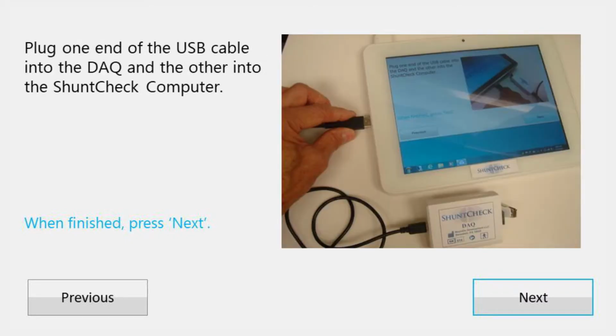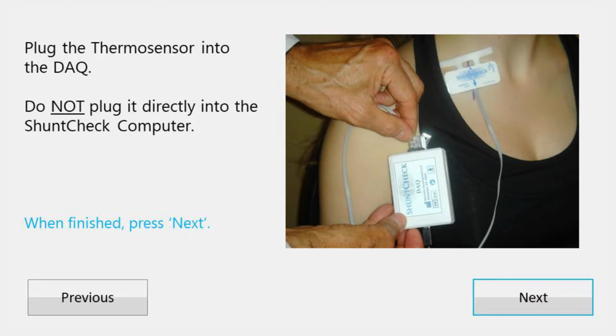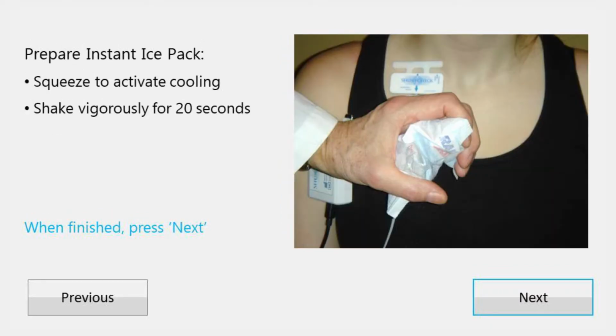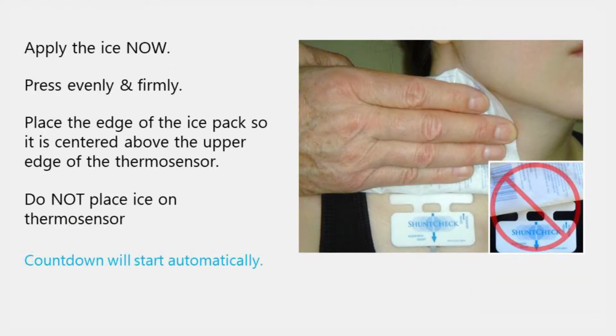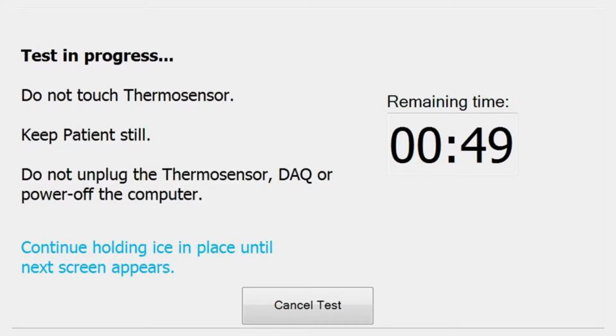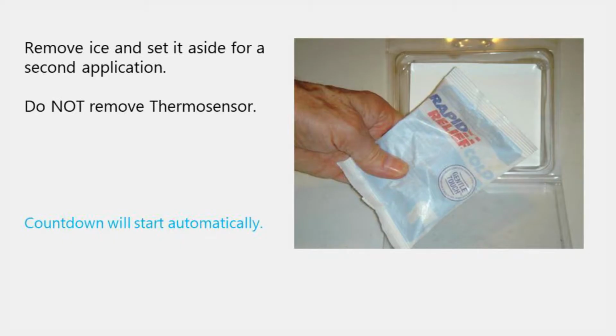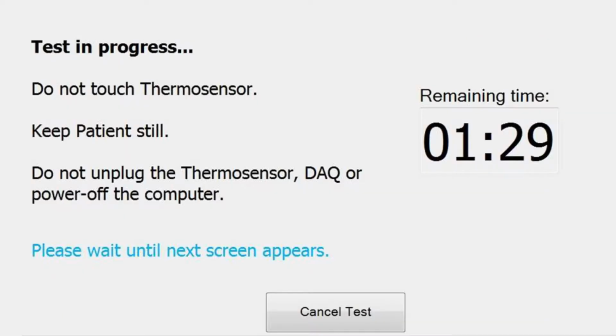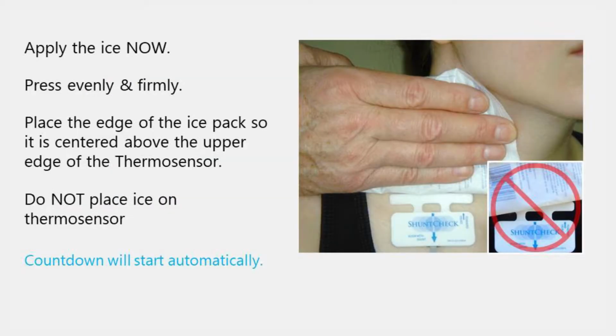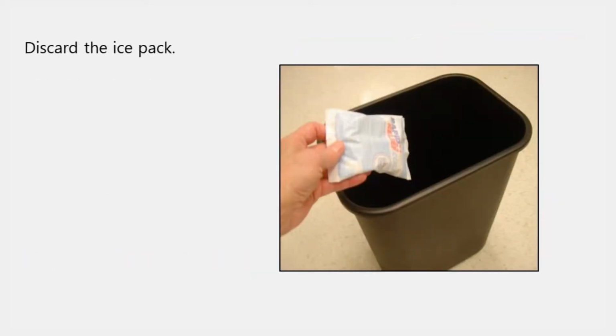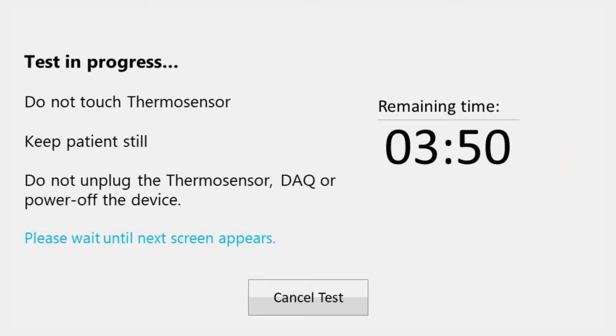Connect the laptop or tablet to the ShuntCheck DAQ, which is a small connector box, and plug the sensor into the other end of the DAQ. Pop and shake the instant cold pack to activate it. Place the cold pack just above the sensor, and the software will count down 60 seconds. At the end of that countdown, set the cold pack aside. The software will count down another 2 minutes. At the end of that, you place the cold pack a second time, this time for 2 minutes.